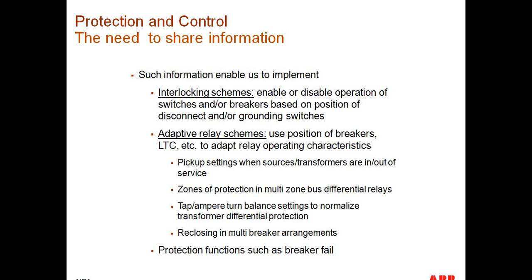The settings on a transformer differential relay are based on the MVA rating, or the ampere-turn balance settings are based on the MVA rating, and then the voltage level of winding 1, winding 2, or winding 3 in the case of a three-winding transformer. CT ratios are also part of that equation as well. But the key is that when a load tap changer is in place, that turns ratio relationship changes. One way that is accounted for is by desensitizing the minimum pickup and slope settings of your transformer differential relay. One thing that is done is to monitor the position of that load tap changer and adjust the ampere-turn balance calculations or settings inside of the relay, so that we do not need to desensitize the relay and can have more sensitive protection.